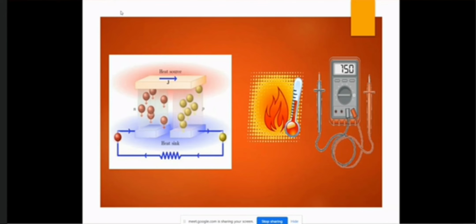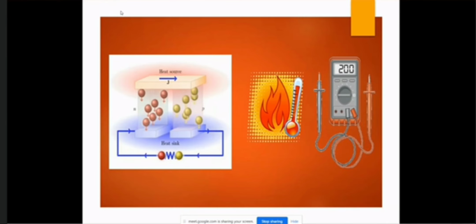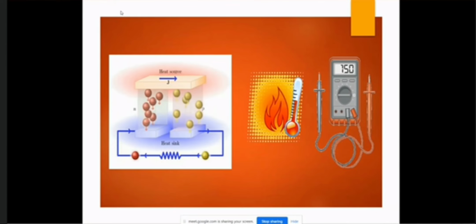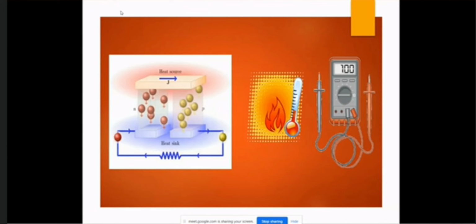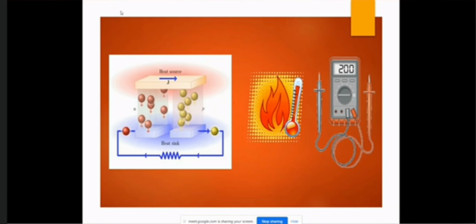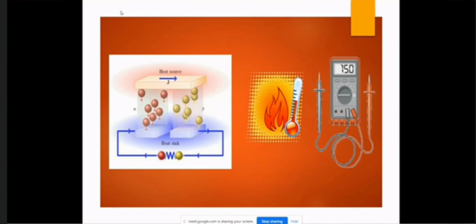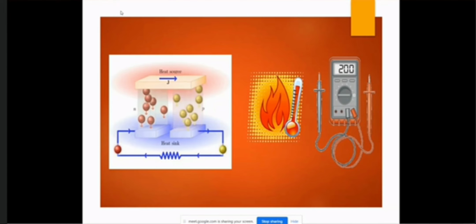Another key factor is temperature. As the calibration quality directly depends on temperature measurement accuracy, two high-precision thermocouples are placed directly at both junctions. They are small to minimize time delay due to heating. An argon atmosphere prevents measurement errors because of chemical effects at the sample surface and platinum wires. Characterizing both standardized type K thermocouple legs shows a maximum measurement deviation of the measured thermovoltage of 1.5%. Over to Ankur.